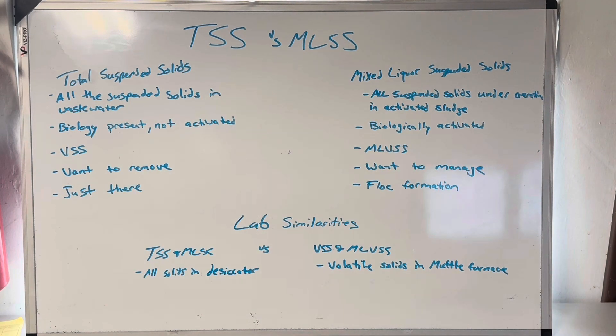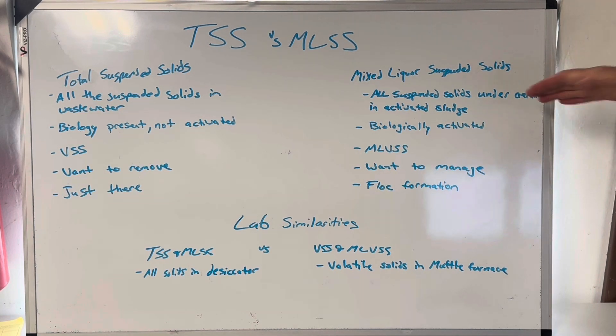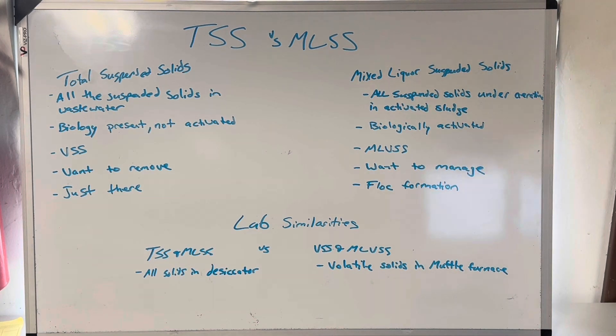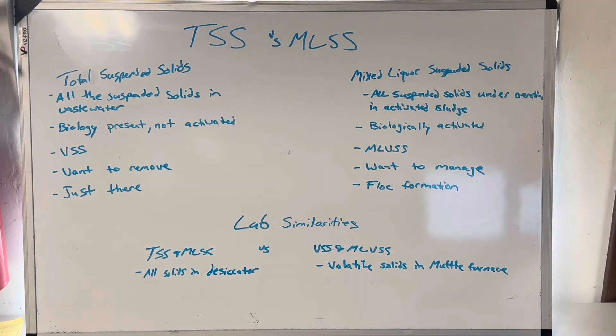MLSS is the mixed liquor suspended solids. That is a specific definition — it is all suspended solids under aeration in an activated sludge plant. You do not have MLSS in a trickling filter or a pond; this is a specific term to activated sludge. I say 'under aeration' but I'm also including the solids in the clarifier, though you shouldn't be keeping a five-foot sludge blanket in your clarifier. You shouldn't really be keeping a lot of inventory in your secondary clarifier — the little bit you have should be returning to aeration very quickly.